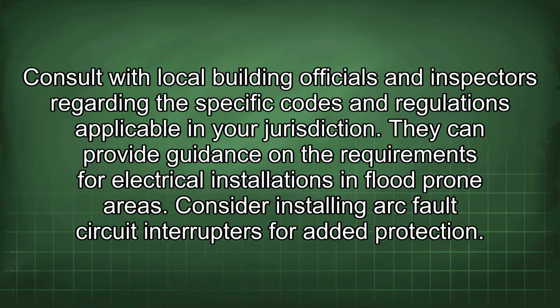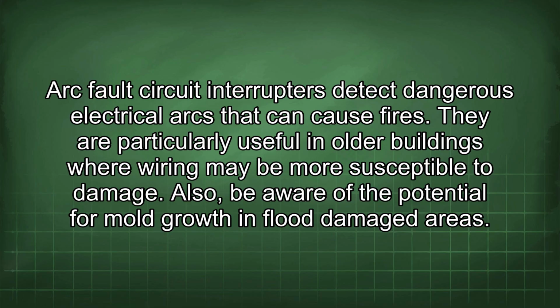Consult with local building officials and inspectors regarding the specific codes and regulations applicable in your jurisdiction. They can provide guidance on the requirements for electrical installations in flood-prone areas. Consider installing arc fault circuit interrupters for added protection. Arc fault circuit interrupters detect dangerous electrical arcs that can cause fires. They are particularly useful in older buildings where wiring may be more susceptible to damage.